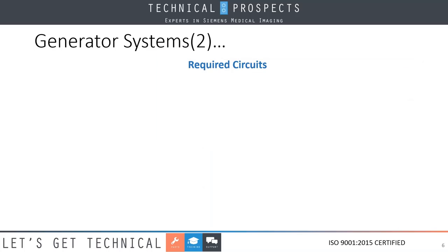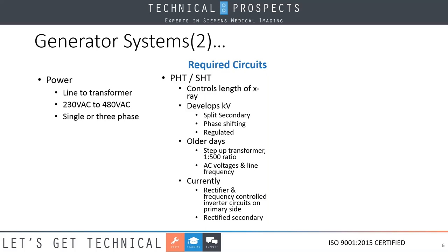So starting with that, let's take a look at the required circuits. The first one is obviously our power circuit. This is what we call the line to transformer circuit. This can be anywhere from 230 volts AC to 480 volts AC, and older units were single phase, but our current systems today are predominantly 3-phase. 2 other circuits are what we in the industry call PHT and SHT. This stands for primary high tension and secondary high tension.